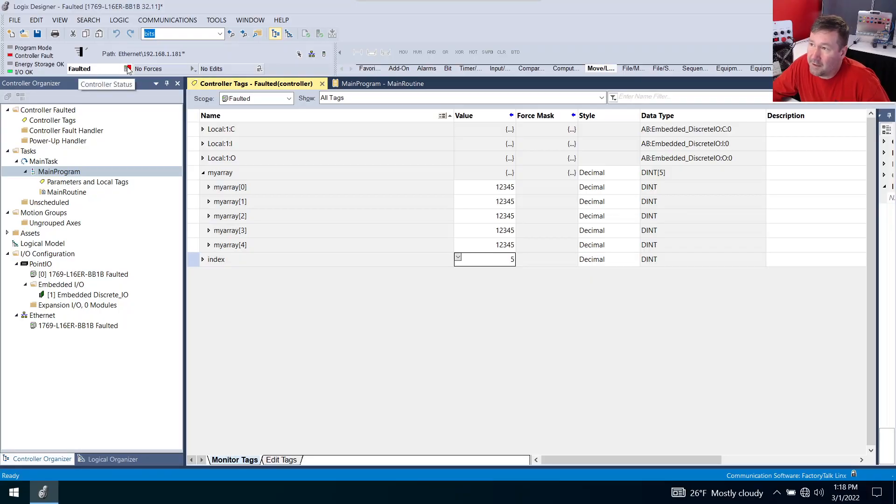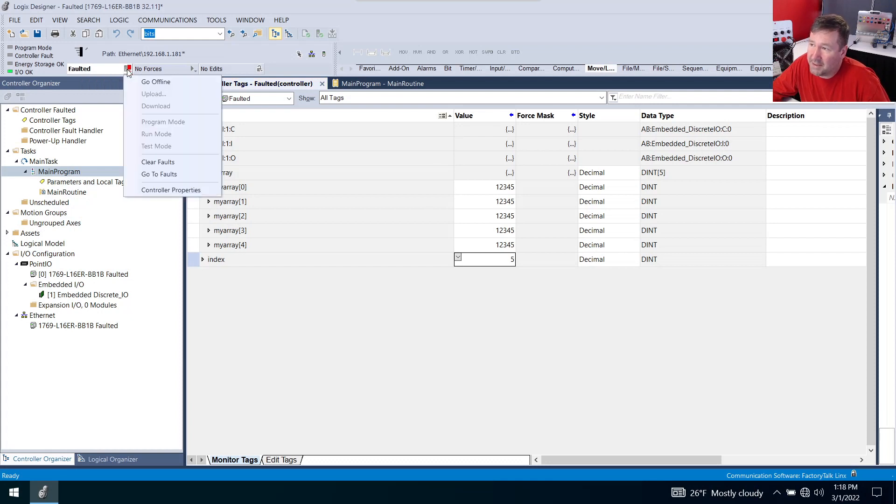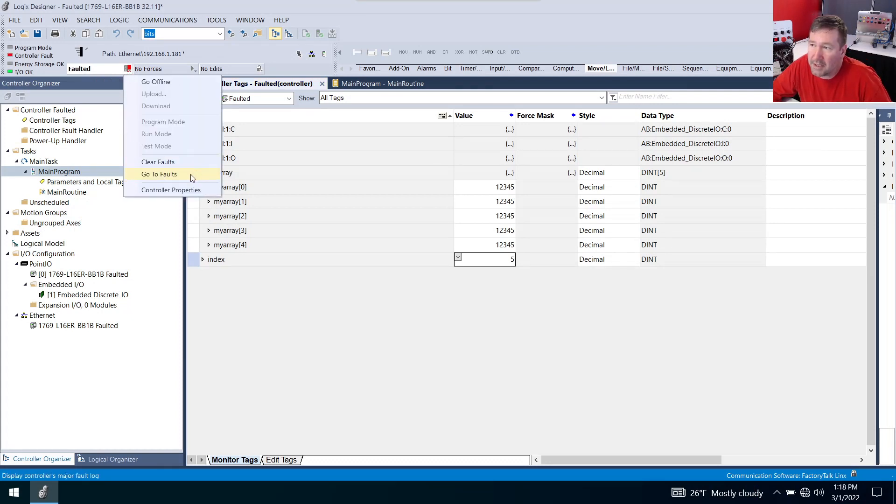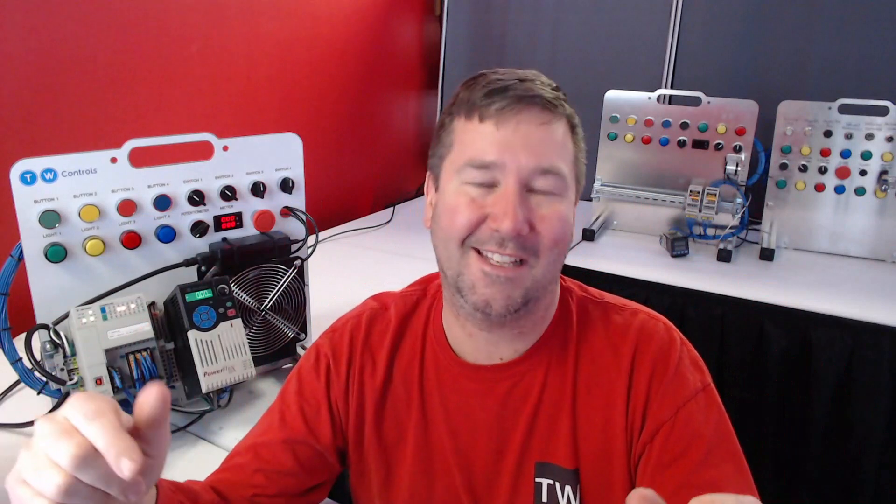Right beside faulted you see it has a red drop down. If you hit that you're going to have two options: clear fault and go to fault. And guys this is one time I have got to stress to you do not hit that clear fault button until you have gathered as much information about this fault as possible.